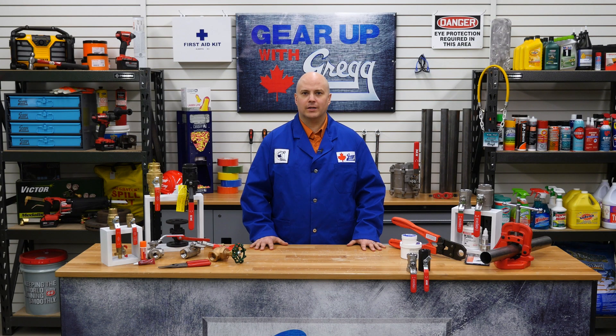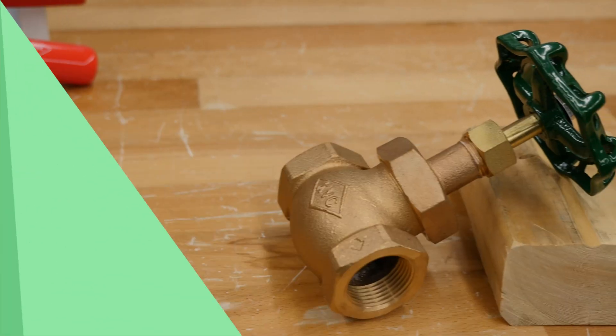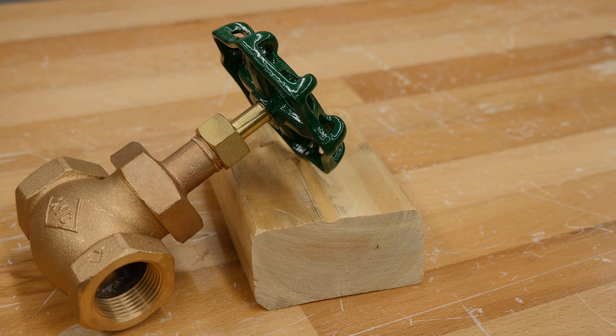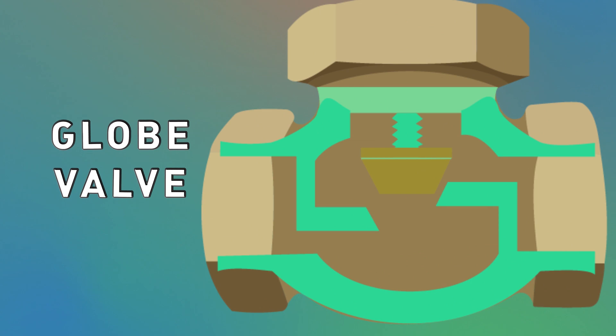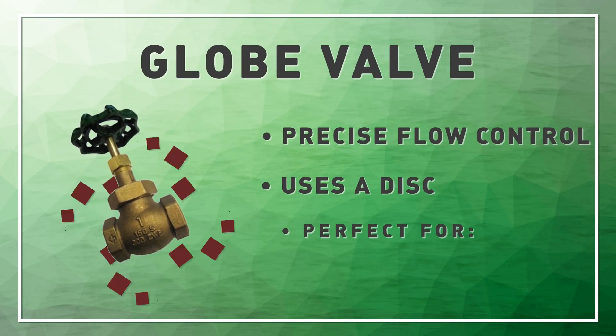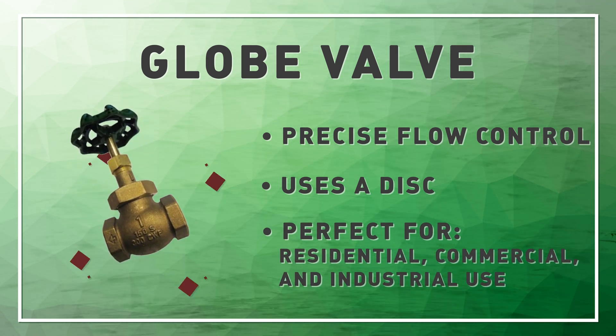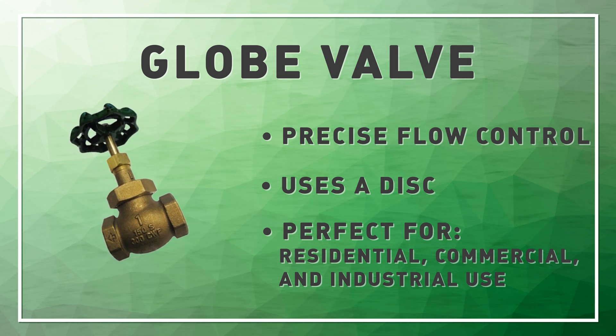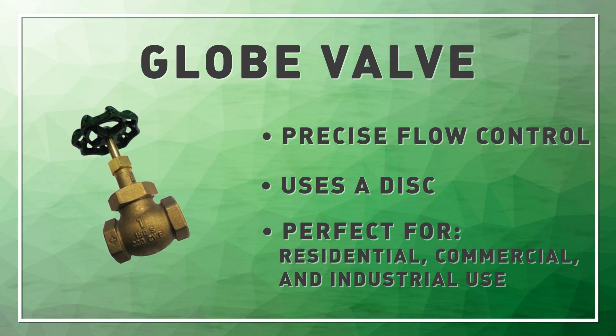Ball valves are great for quickly stopping and releasing the flow of your system. But what if you need precise control of the flow? If that's the situation, a globe valve is what you are looking for. As you can see here, the system uses a disc which goes up and down depending on which way you turn the handle. When the system is closed, the disc sits on the bottom, sealing off the flow from going forward. So unlike the ball valve, the user will have precise control of the system's pressure depending on where the disc is positioned. You will also notice a drop in pressure compared to a ball valve due to the 90 degree angle the flow passes through. This makes globe valves perfect for residential, commercial, and industrial use.